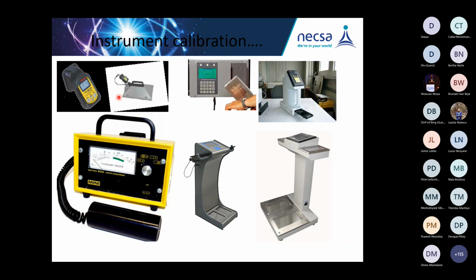And this is a floor detector, which is an actual scintillator detector. There's a tube inside that tube that I was saying that if it breaks, then the instrument is no longer fit for the purpose. And the unit, when you scan the floor, will be in becquerel per square centimeter. This is the likes of the CM9 and the CM11, how they look.